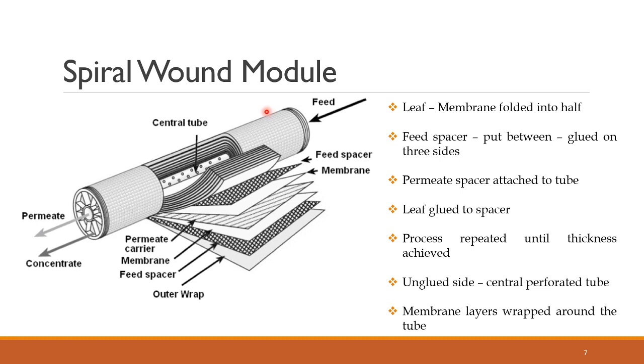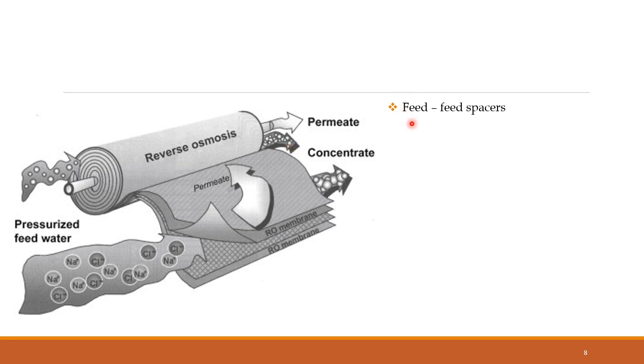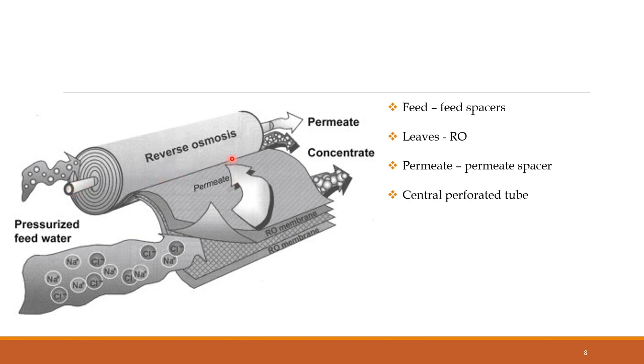Now we will see how reverse osmosis takes place in this setup. The feed is introduced through the feed spacers. The leaves are where the actual reverse osmosis process takes place. The dilute water — the permeate — comes out from the other side of the RO membrane and is carried through the permeate spacer, which is connected to the central perforated tube. The permeate collects in that central tube and flows out from there.